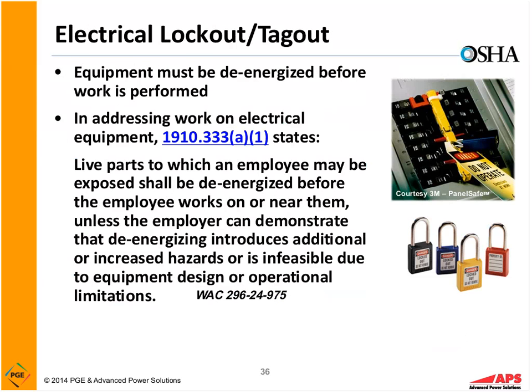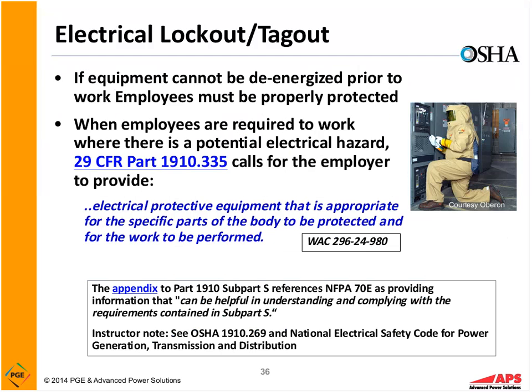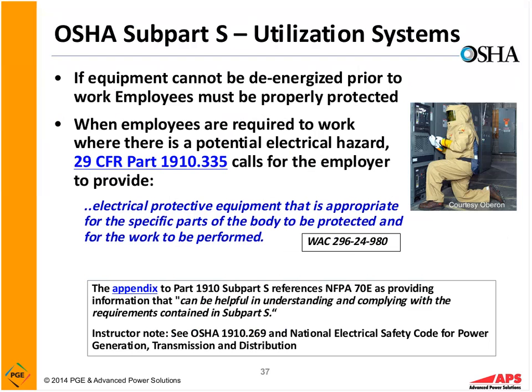Lockout, tagout. Equipment must be de-energized before work is performed. So we look at this in addressing work on electrical equipment. 1910.333(a)(1) states live parts to which an employee may be exposed shall be de-energized before the employee works on or near them, unless the employer can demonstrate that de-energizing introduces additional or increased hazards or is infeasible due to equipment design or operational limitations. So in summary, what are they saying? Shut it off. What's the safest way to work on anything? To turn it off. So there are some exceptions to that, to turning parts off, such as testing and troubleshooting, but we're not going to go into all those.